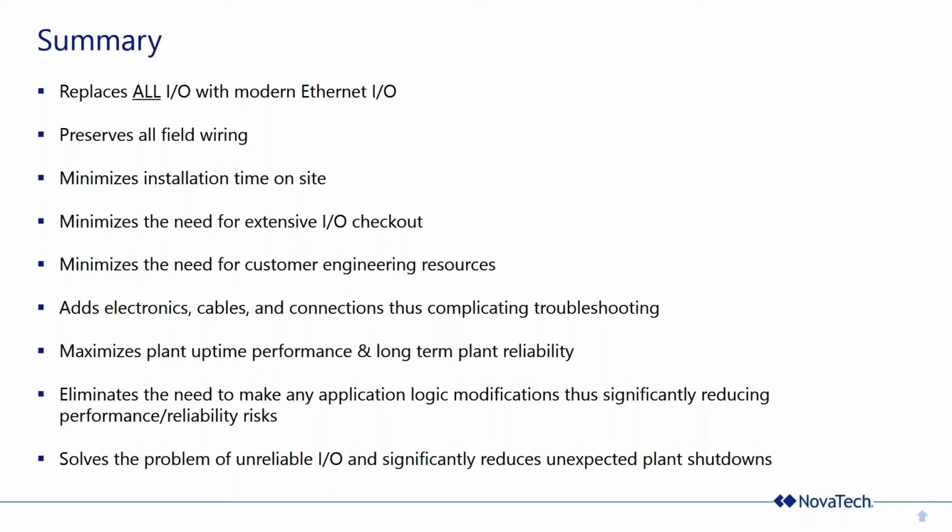Basically, all you have to verify is that one of those points is the correct point on the card, and you're pretty much done. But it does add cables, connectors, electronics. It keeps the existing edge connector in there, though that's a simple device. But it does add more electronics and could complicate troubleshooting in the future. So that's the downside. So if you need something done very, very quickly, this is faster than doing the rewiring, but it does add additional components that you'll have in there for the life of the installation.